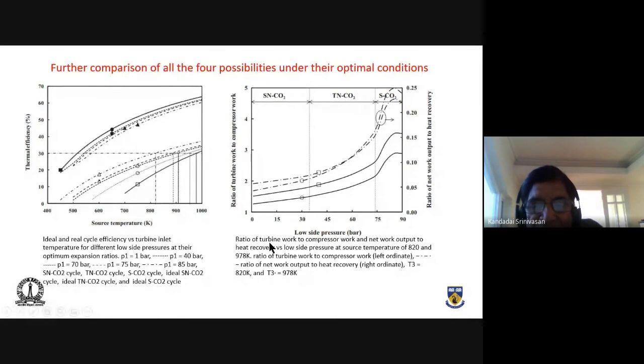Now, what I mentioned earlier, the compressor work is a kind of parasitic work. The power generated is like income tax: if you're earning something and the taxman takes over 60% of it, that's not very appropriate. The turbine works hard to produce about 100 megawatts, and the compressor takes away almost 60 megawatts. So you can see the turbine-work-to-compression-work ratio for various low side pressures.